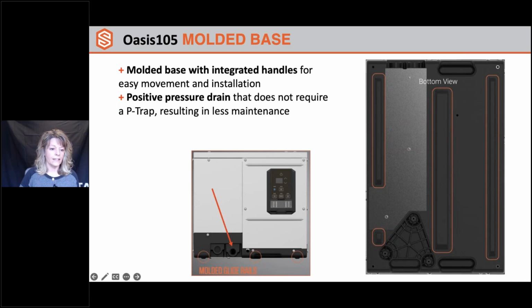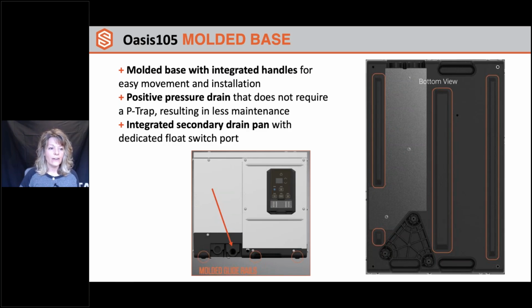Here's where you get the positive pressure drain that does not require a P-trap, which means significantly less maintenance when you're not having to deal with a P-trap. And then here is that secondary drain pan dedicated float switch port. If you're going to utilize that, you're going to have to open that up. It's just a punch out there. And then there are float switches on the market that can screw right into that and then wire to the dehumidifier. So very excited with that.